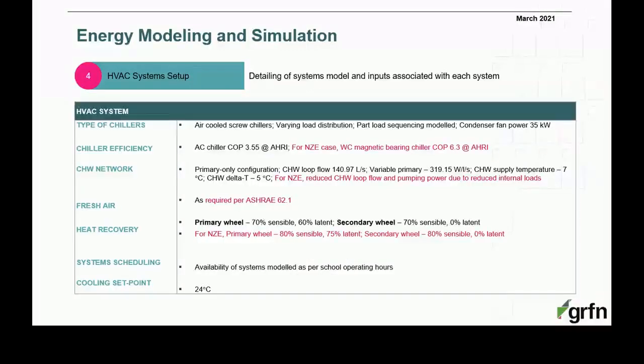For the HVAC system setup, for the original design, it was using air-cooled screw chillers with a COP of 3.55 at AHRI conditions. For the net zero energy case, we're using magnetic bearing chillers with a much higher COP and a very good part load efficiency. For the chilled water network, both are variable primary. The delta T for the original case was 5 degrees C. For the net zero energy option, it was 9 degrees C to reduce the pumping power.